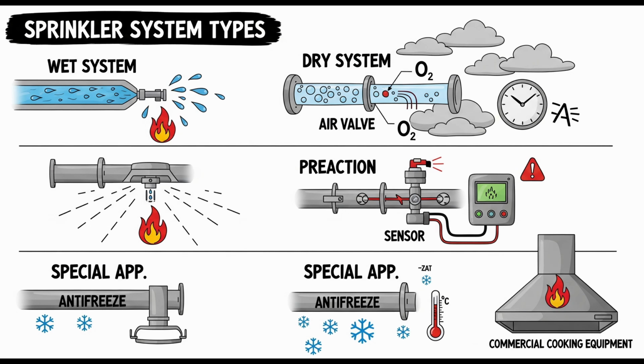We talked about ESFRs needing specific performance. Why the general prohibition with antifreeze? ESFR sprinklers rely on a very specific high-momentum spray pattern to penetrate the fire plume and suppress challenging, high-piled storage fires quickly. The physical properties of an antifreeze solution, its viscosity, its density, how it atomizes when sprayed, could potentially alter that critical spray pattern. This could compromise the sprinkler's ability to suppress the fire effectively, as designed. So they need specific testing and listing together to prove compatibility. That makes sense. Their performance is very sensitive to the fluid being sprayed.